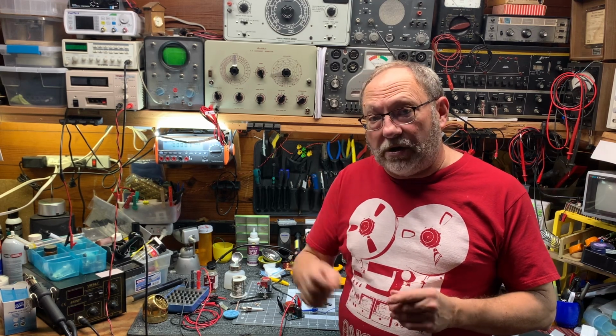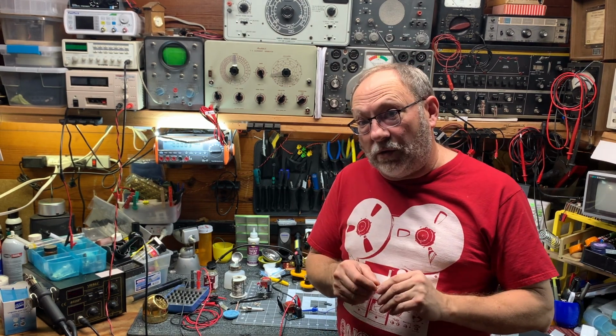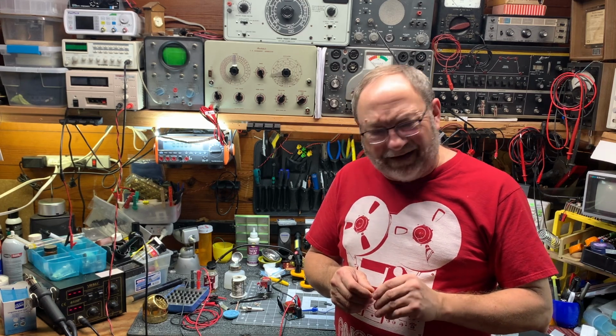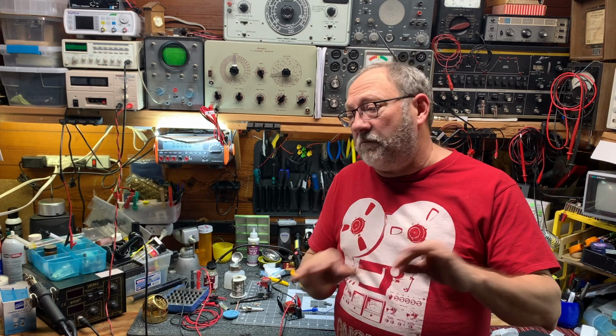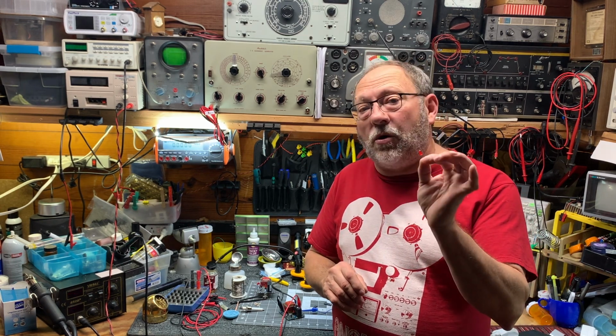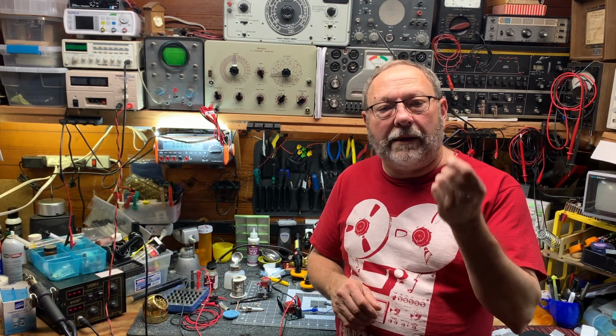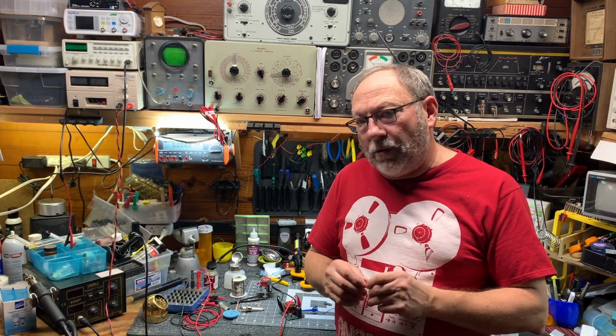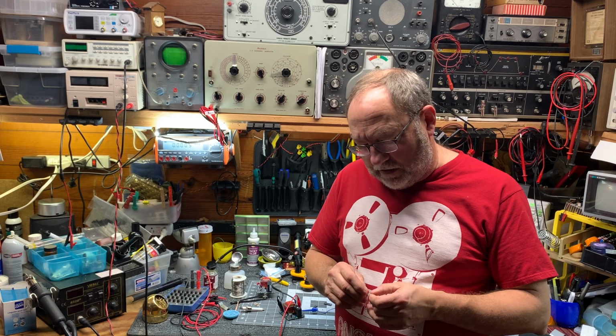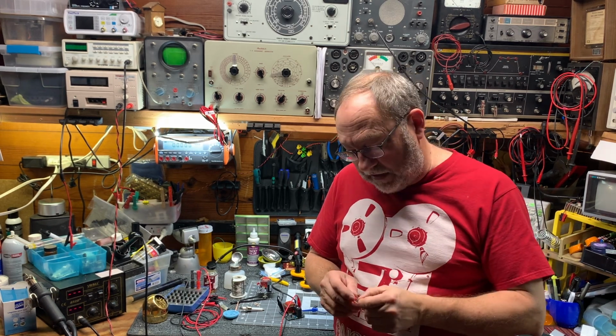And that's what this story is. After a lot of troubleshooting, we kept coming back to a bad LED, which was in series with the relay coil. And got tested with the scope and with meter and all of this, and we just finally came back and said, you know what, even though the LED glowed slightly, just a little bit, maybe the LED's bad. Sure enough, that's what it was. So we replaced a couple of components that were popped, and we finally replaced the LED, and we got the module working.